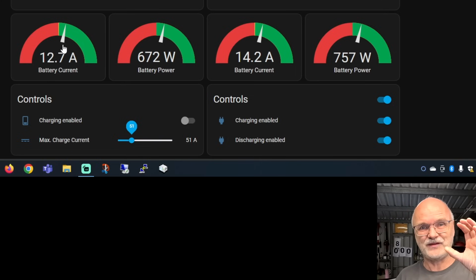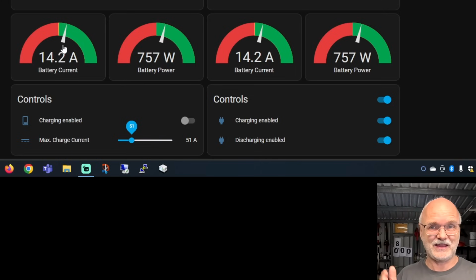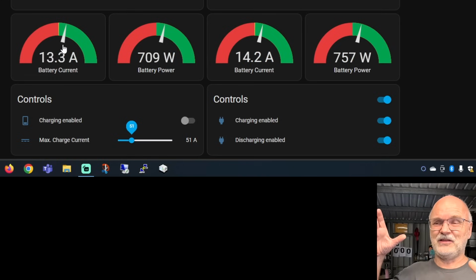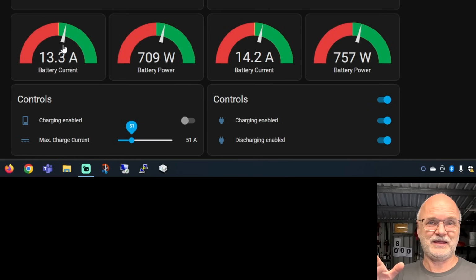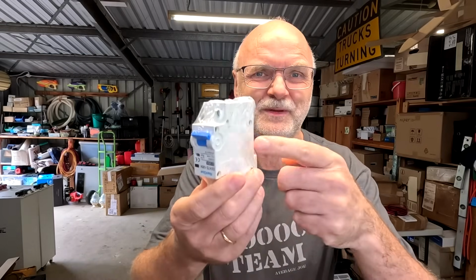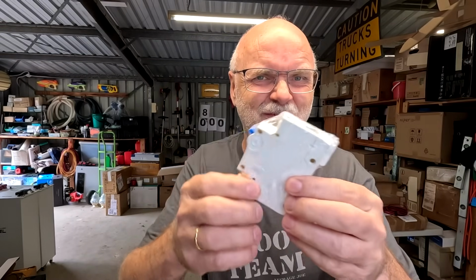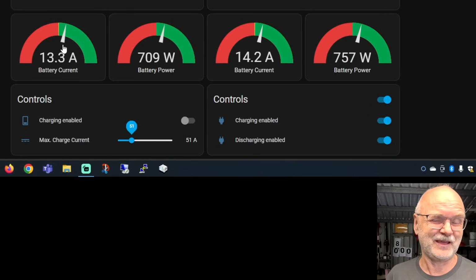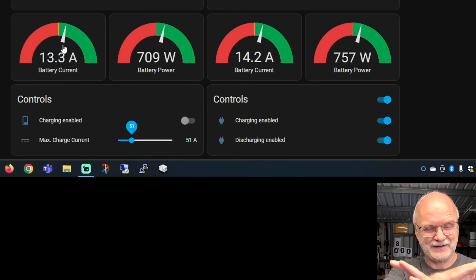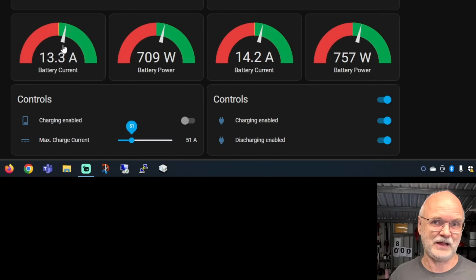The BMS is a safety device, and you probably shouldn't have any third-party integration or hardware interfering with your BMS. It's like opening one of these circuit breakers and trying to modify it, or put an LED in, something like that. It's a safety device, it should stay as it is. I think of the BMS the same way as this breaker: if something goes wrong, current, temperature, voltage, it disconnects your circuit, it disconnects your battery.